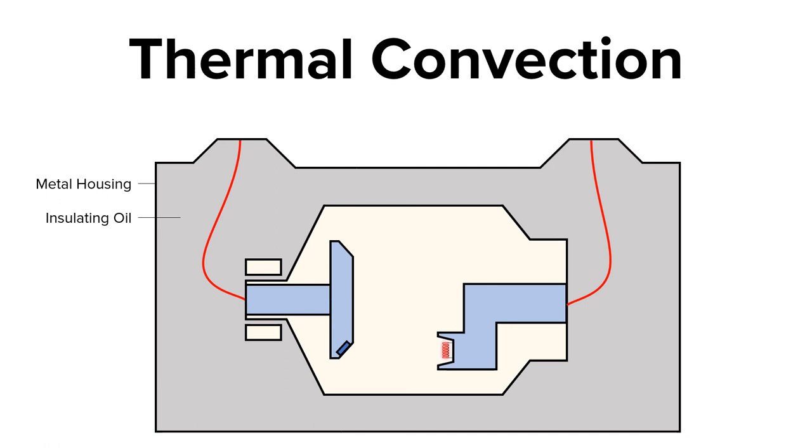The last way to remove heat from the x-ray tube is through thermal convection. Thermal convection is moving heat through air or liquid. For example, the heat that travels to the stator will dissipate into the insulating oil of the metal housing.